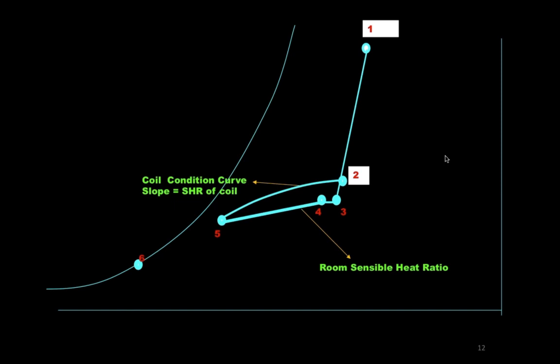That is, if the design condition is correct, and the problem is right at the early design condition, the very first starting point. We notice in most situations that the condition is not quite right, simply because the nature of consulting practice is such that we tend to build in factors of safety along the way. So the issue of over-design, without elaborating much on how it comes about, is not uncommon. We would find that the coil that gets selected is already an over-designed cooling coil. The chill water flow rate is probably not the right value for the actual condition that we will be experiencing when the building is commissioned. So the issue of over-design is a very big challenge.